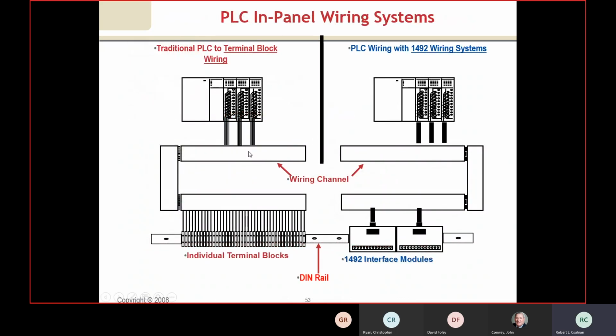This just shows the unit, the way it's wired in the panel. I don't have a slide here, but for any of you converting over from a PLC-5 or an SLC 500 to the newer Compact Logix, we've got a whole system set up that allows you to utilize the existing I/O wiring and switch over the whole unit from the older controller to the newer one. If you've got time limits, like a weekend shutdown, you can just imagine the amount of errors you might get into rewiring all the I/O modules. So there's a way to do that - I don't have it displayed here, but that's certainly information I can get you if you're interested.